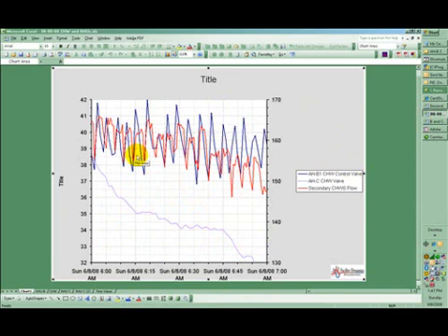So I guess I'm proposing we do a test here where we lock down the B valve command and see if the flow stabilizes. And if it does, then I think we really need to look at how to fix that problem with the B system. It could be it's just some loop tuning, but it could also be the valve's so sensitive that it has so much authority in the system right now.